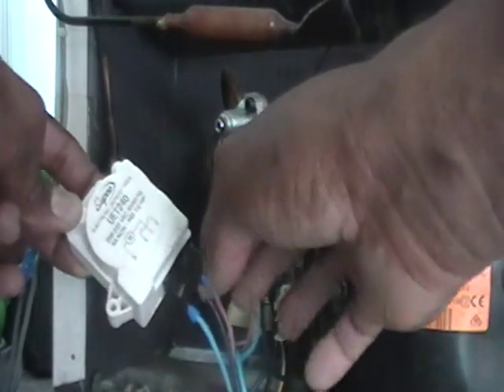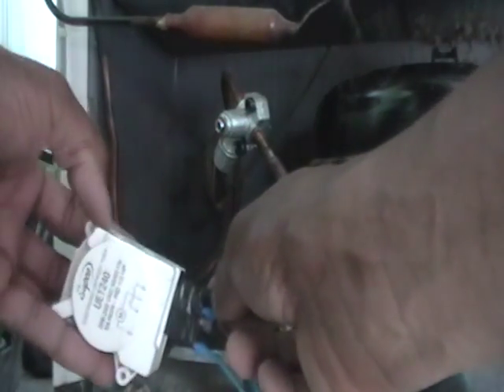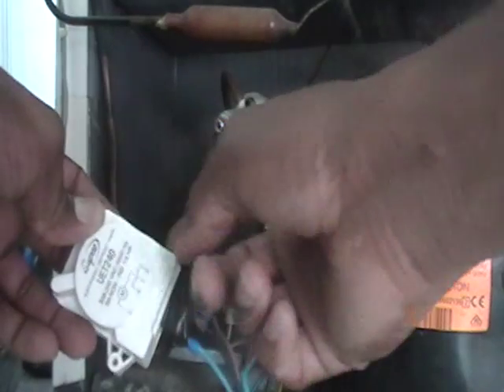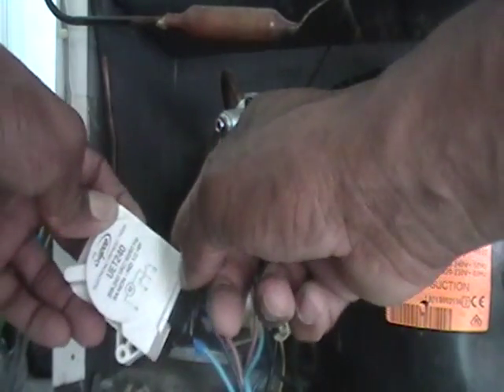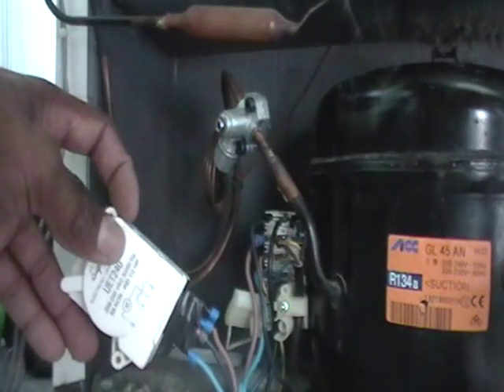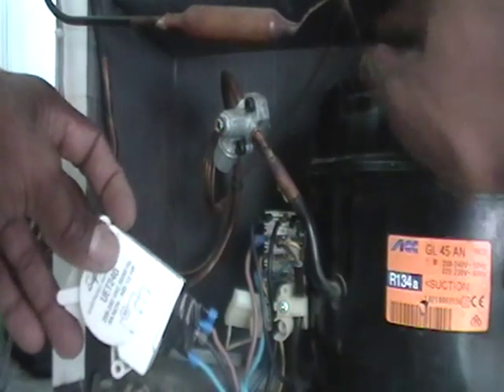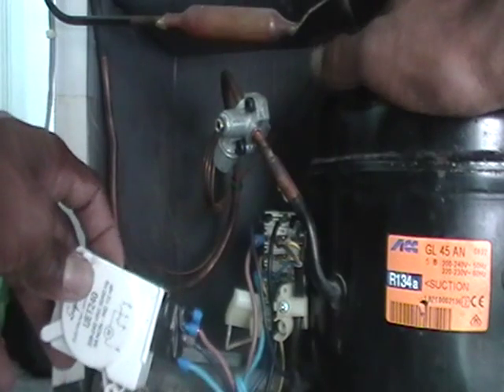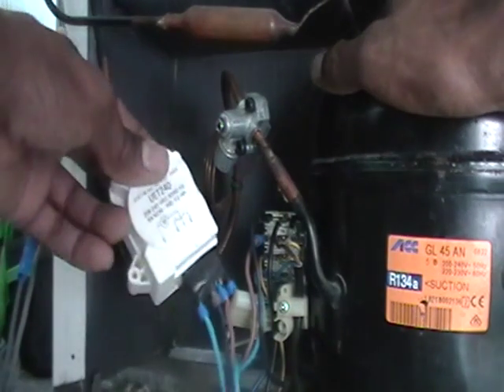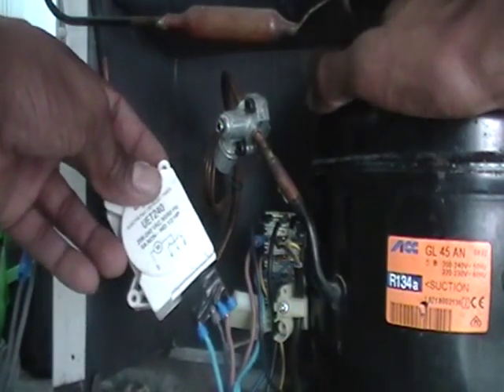So whenever it's set, it will stay there for about 35 minutes. It has a runtime of 4 hours, set to 4 hours, and a defrost time set to 35 minutes. So my freezer was basically running for 4 hours, and then resting for 35 minutes, so to speak.